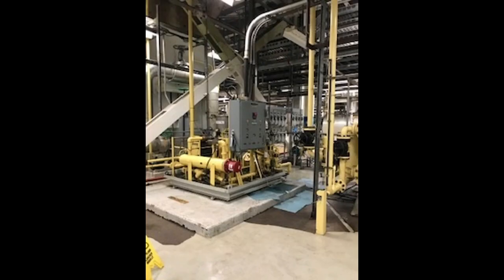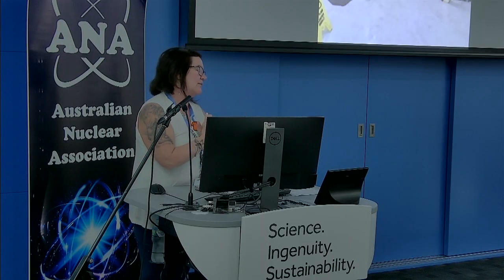And the turbine lube oil is directly tied to the generator seal oil. So the turbine lube oil keeps those bearings lubricated, and the generator seal oil keeps the seals full of oil so that the hydrogen does not escape into the turbine building, which of course would be a very big fire explosion hazard. So this is on the secondary side, one of the most important safety parameters that we have to monitor.